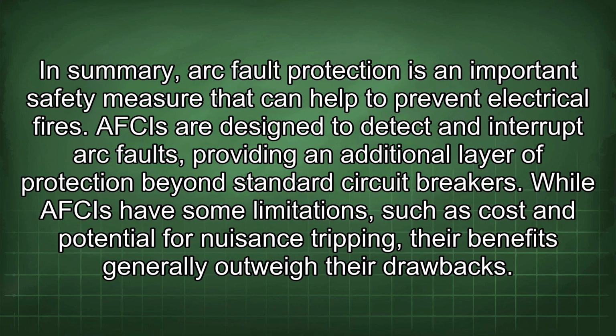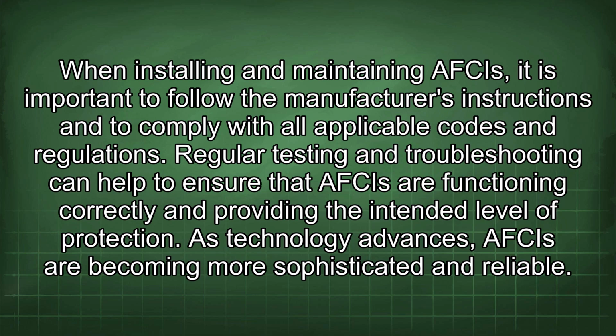In summary, arc fault protection is an important safety measure that can help to prevent electrical fires. AFCIs are designed to detect and interrupt arc faults, providing an additional layer of protection beyond standard circuit breakers. While AFCIs have some limitations, such as cost and potential for nuisance tripping, their benefits generally outweigh their drawbacks. When installing and maintaining AFCIs, it is important to follow the manufacturer's instructions and to comply with all applicable codes and regulations. Regular testing and troubleshooting can help to ensure that AFCIs are functioning correctly and providing the intended level of protection.